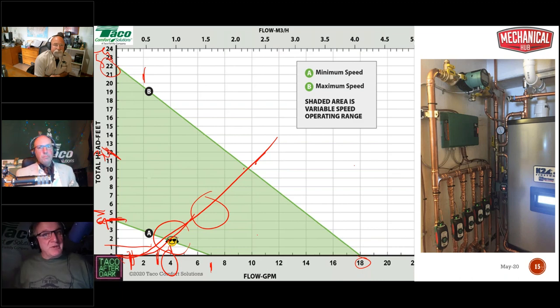Now, does this work with outdoor reset mod-con boilers? Does it fight with outdoor reset? No, it doesn't care what the water temperature is. It's not trying to set the water temperature. It's just watching the difference between the two, the difference between what's going out and what's coming back. It doesn't care what that temperature is.